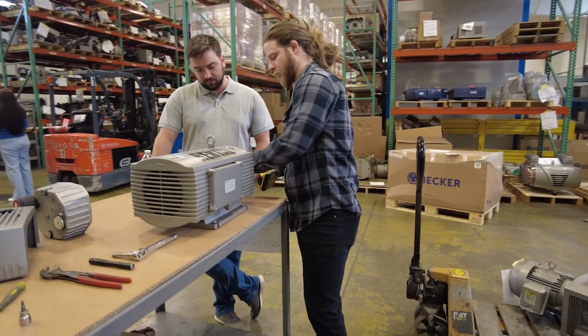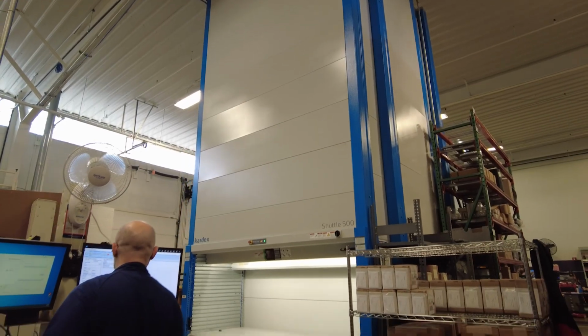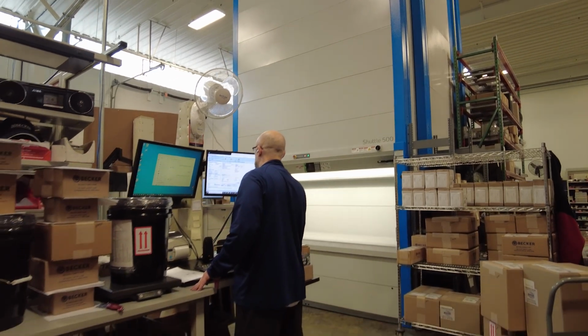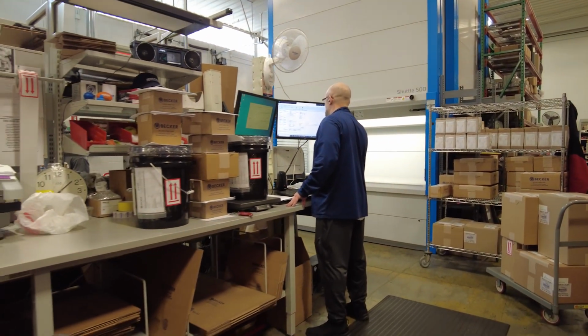It's important to know what your voltage is and to make sure you're getting adequate voltage supply. So 208 volt, three-phase power is very common in the United States, but we see a problem where the voltage will drop much lower than that to 200 volts or below. And the pumps can't run off of that voltage typically. Most of them cannot. It's not sufficient power to run the motor. So what will happen is the pump will intermittently trip off or shut off while they're running. And the customers will call and be confused about why the pump's not running. And usually it's just that they don't have enough voltage. In those cases, we always suggest they talk to someone who can help them boost their voltage, either with a transformer or some other device that just gives them a little more power and keeps the voltage more steady for the pump.